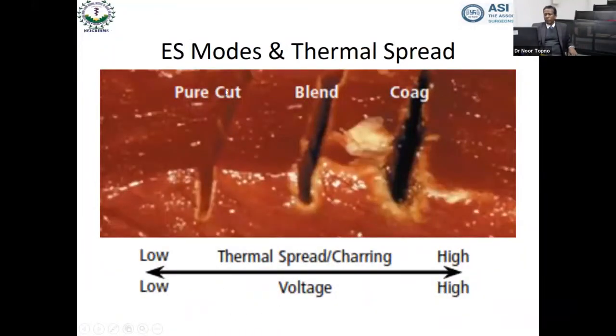This is a very important slide. In the pure cut mode and the coagulation mode at the other end of the spectrum, we are talking about how the thermal spread happens. In the pure cut mode, the lateral damage or the lateral thermal spread is much lower as compared to coagulation mode. What is important from this slide for us to know is, it is always preferable to use the cutting current whenever possible rather than use coagulation, especially when you're doing surgeries in critical areas. Sometimes we use the coagulation current also to do cutting, which is not a desirable thing to do.